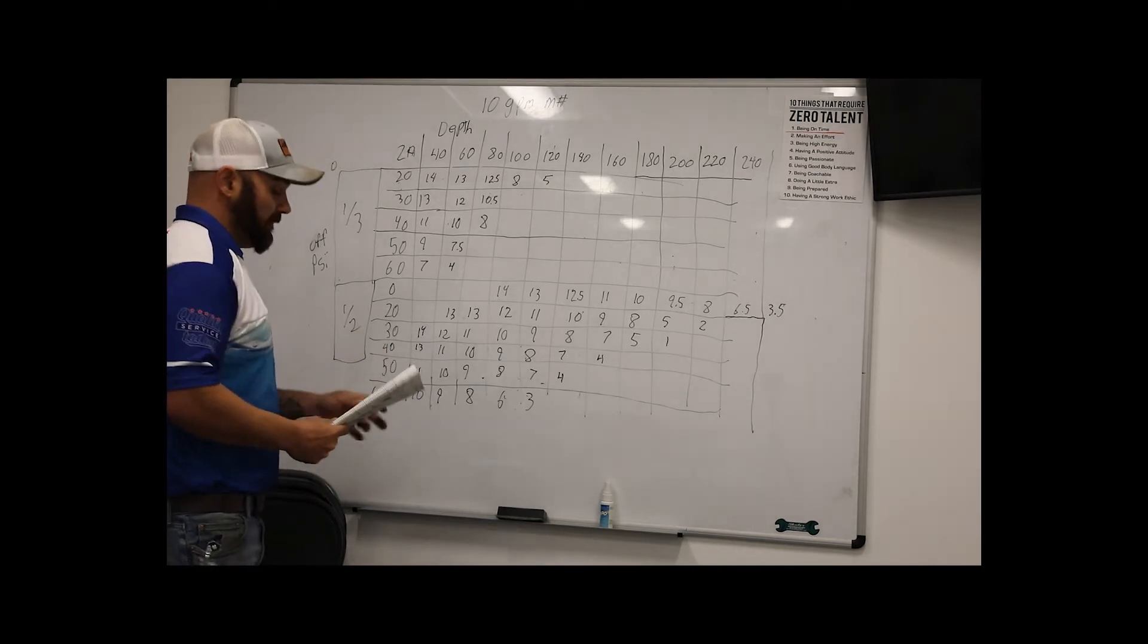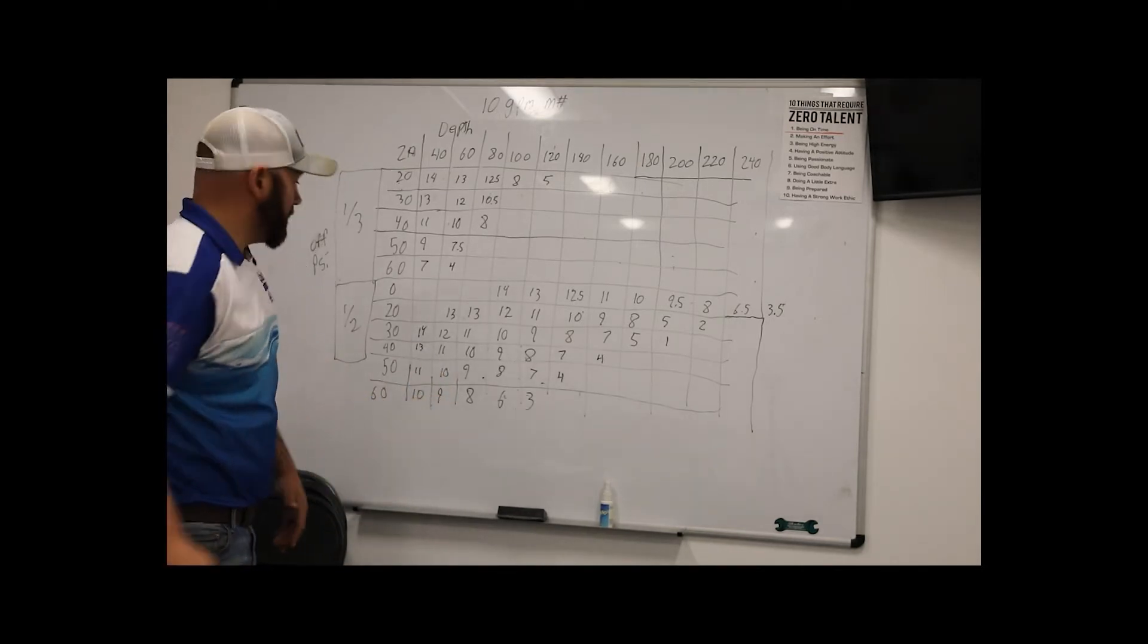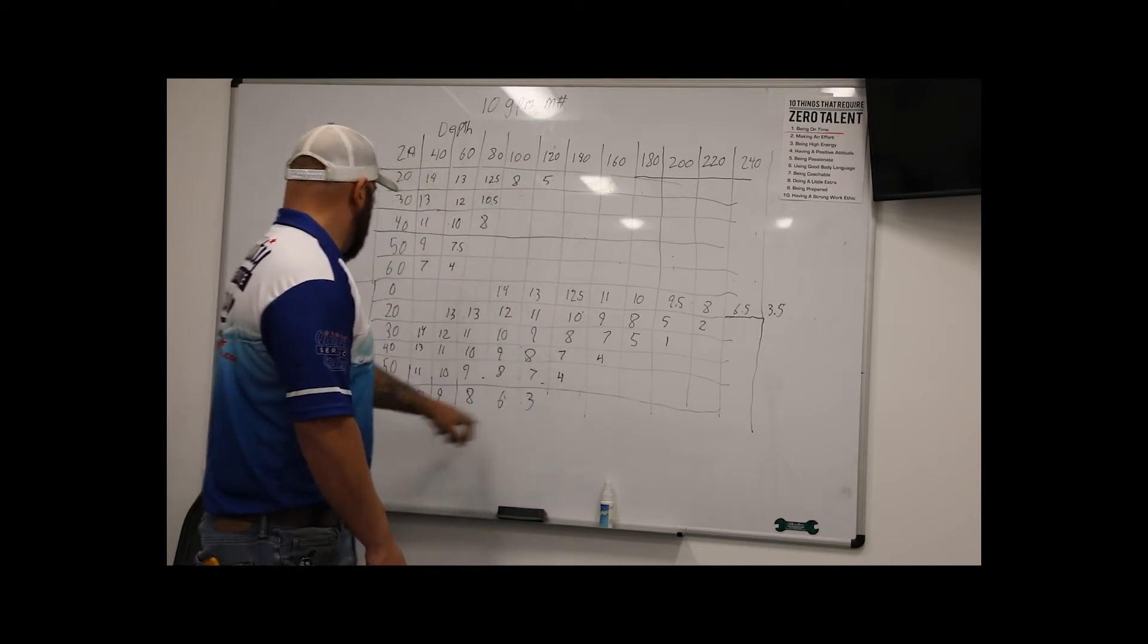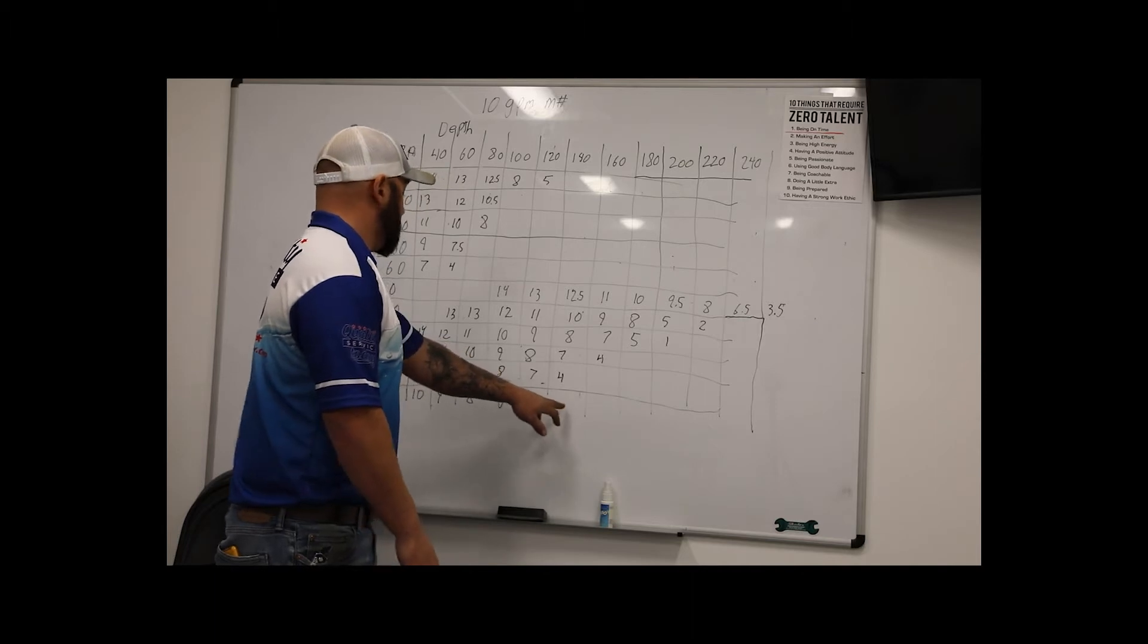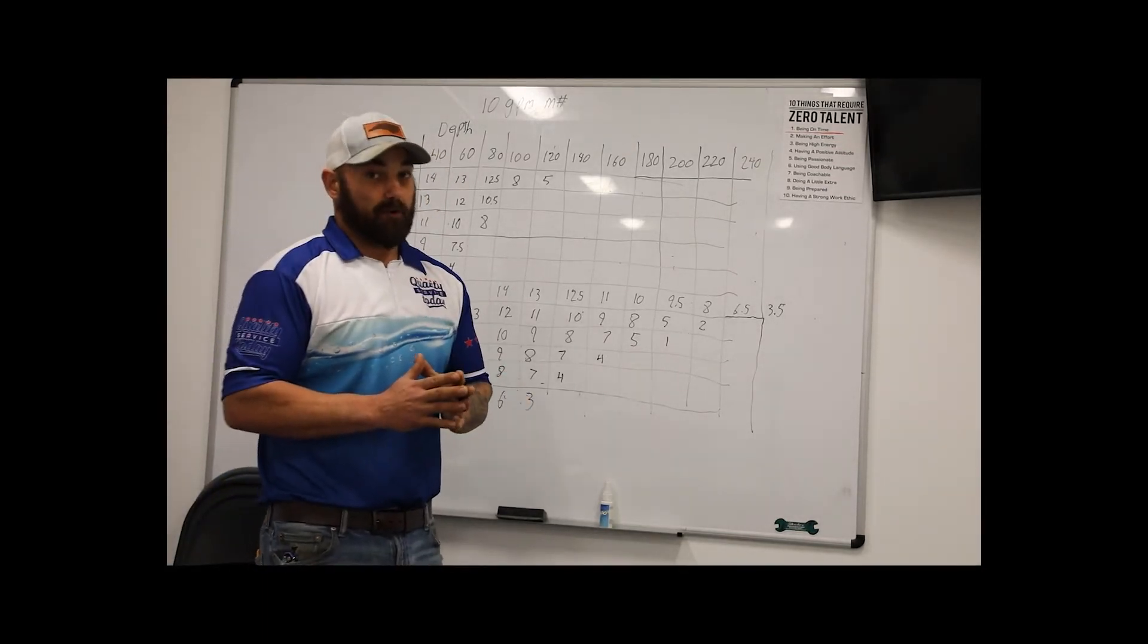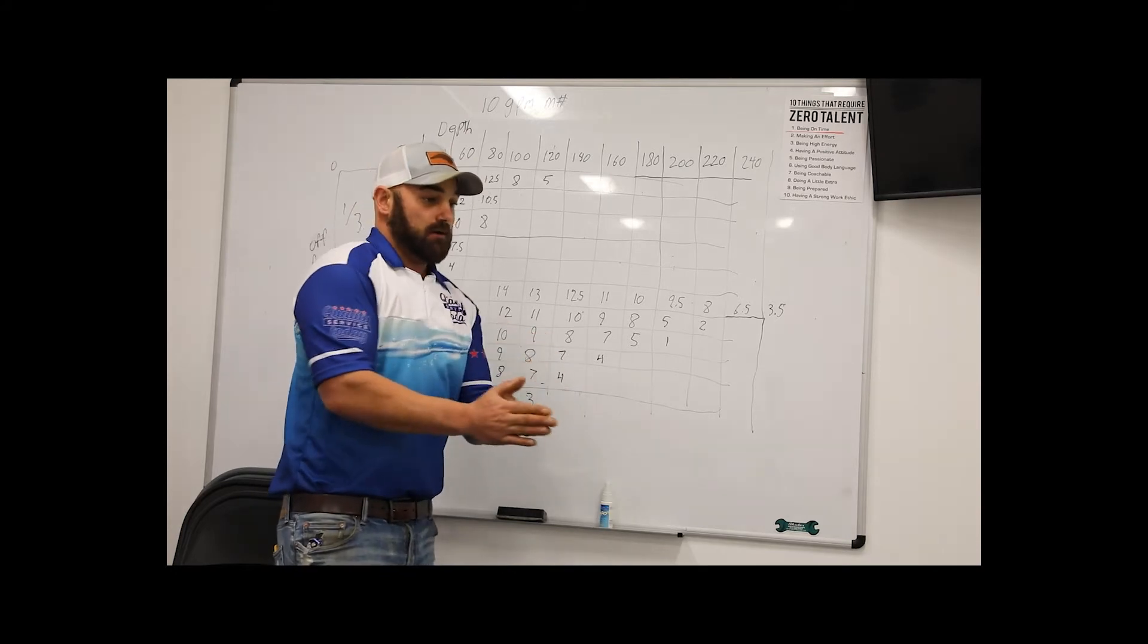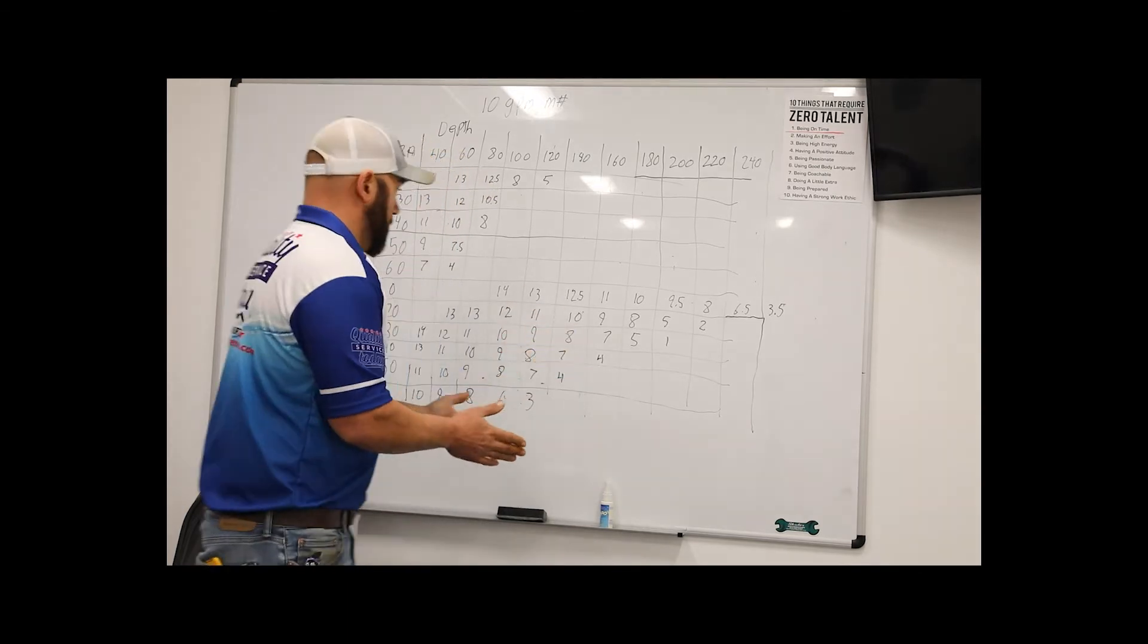So these have some unrealistic numbers that are used in other applications. We're going to stick to typical residential. Your typical residential is going to be a minimum of half horsepower. Your 5-gallon-a-minute is going to pump deeper than your 10-gallon-a-minute. So I'll get into this, and then I'll explain the difference in gallons a minute on pumps. So this half horsepower, if we stick it at, we can't, we will pump 3 gallons a minute at 120 foot. So it's 120 foot deep, and my switch shuts off at 60, I'll pump 3 gallons a minute is what it can move. I can't hang it at 140 foot. It's not going to move that water. There again, you need the pump sizing guide for the model you have. So if you're buying it from a box store, I've got a huge disappointment for you. I was in a box store one day, and their horse and a half pump would only hang at 250 foot. It's quality of pumps, how they're made, what goes into them. The box store pumps are not going to work like what I'm explaining here hardly. I mean, you look up the sizing chart for them. They don't work that way.